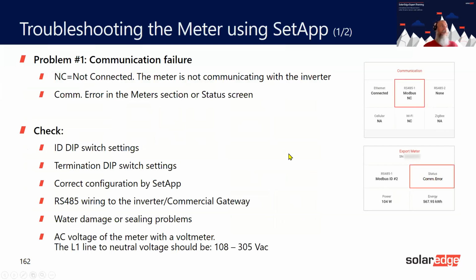Problems. What are you going to come across? The first one is that you're going to see NC, so not connected. And that will be either a cable issue, it will be the ID set to 1 instead of 2, or it will be the CT's not clamped round correctly, and it's not allowing you to record 100 amps or 200 amps or whatever it should be. So what should you do? Check the ID dip switches. Make sure you've got 1 and 3 down and 2 up.